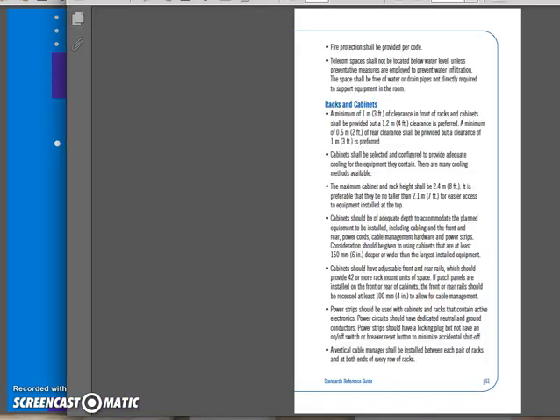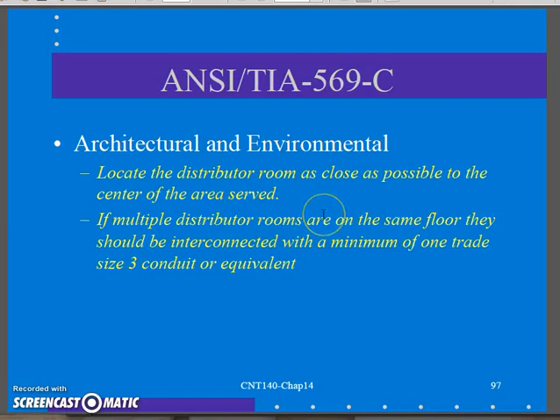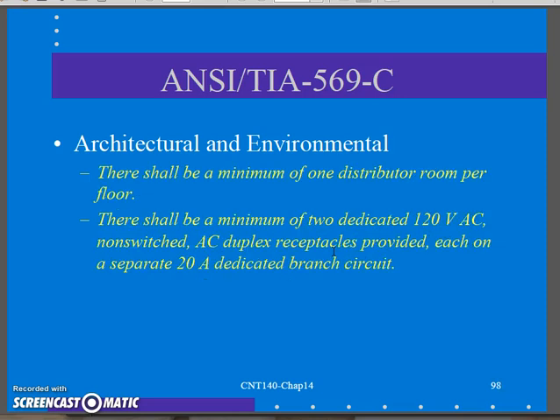Locate the distributor room as close as possible to the center of the area being served — we mentioned that before — as close to the center of the floor as possible to get maximum coverage. If multiple distributor rooms are on the same floor, they should be interconnected with specified conduit so I can run backbones between my closets. There should be a minimum of one closet per floor in the building.